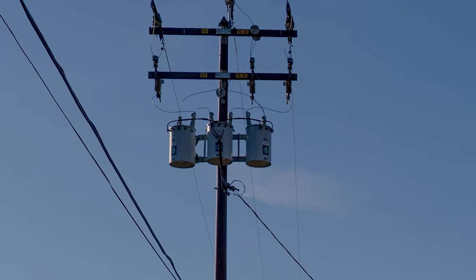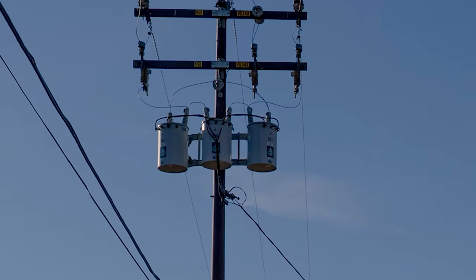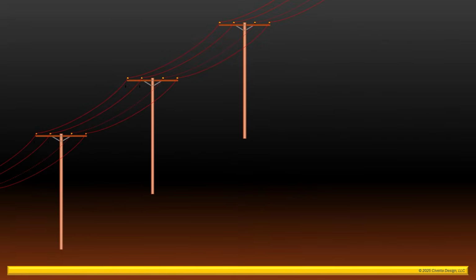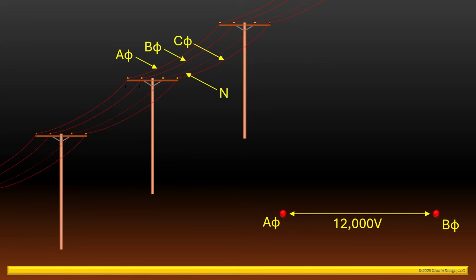Before connecting a three-phase transformer bank to the utility's primary distribution system, let's take a look at that to make sure we understand what we're seeing. I'm sure you've all seen overhead utility poles like those shown. A utility's overhead distribution feeder system is usually comprised of either 3 or 4 conductors, which are often designated as A phase, B phase, C phase, and a neutral conductor. The neutral, however, is not always present.